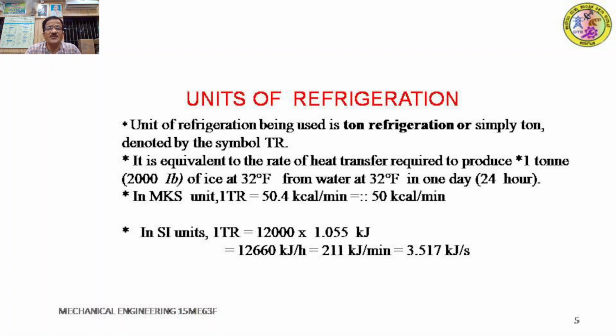Originally in the FPS system, foot-pound-second system, the concept was developed, and that's why it is taken as basis. So 12,000 British thermal units multiplied by 1.055 kilojoule, the SI unit heat value, gives you 12,660 kilojoule per hour.